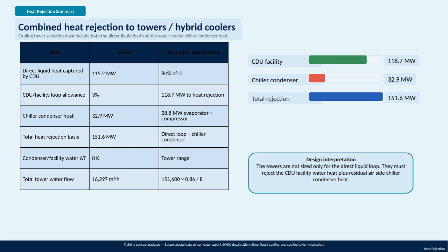When you total these together, the system must reject about 151.6 megawatts of heat. The cooling towers are designed to handle this combined load, not just a direct liquid cooling loop. The water temperature change, or delta T, across the condenser is set at 8 Kelvin, which impacts the water flow rate needed for the towers. This results in a total tower water flow of approximately 16,297 cubic meters per hour. In summary, the design ensures that the cooling towers accommodate all heat sources in the facility, guaranteeing reliable and efficient heat rejection from both the direct liquid cooling and the chiller condenser systems.